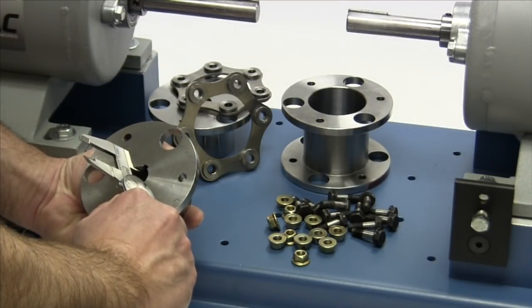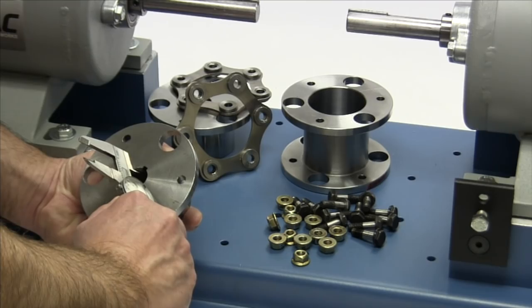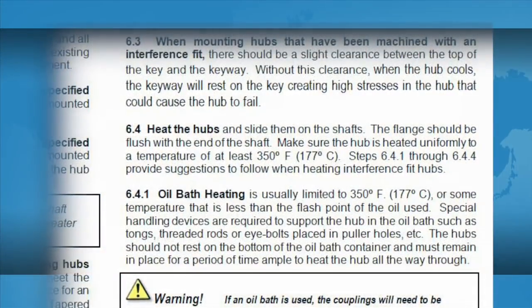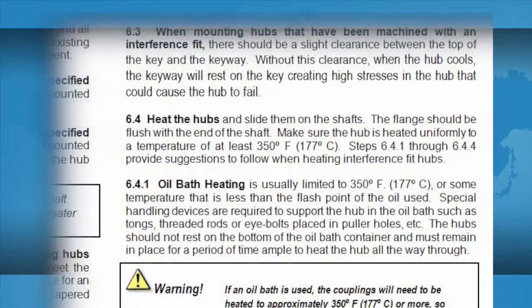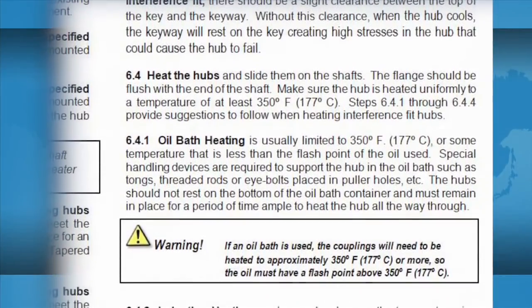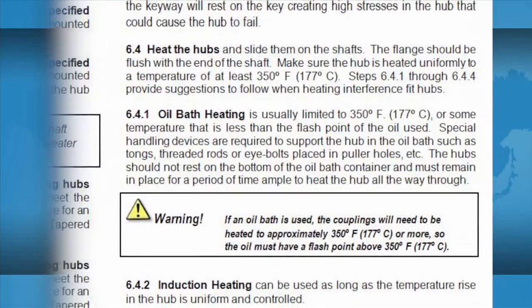You may notice the hubs are bored slightly smaller than the equipment shaft diameters. Unless otherwise specified, Lovejoy manufactures disc coupling hubs with an interference or shrink fit, and the hubs will need to be heated prior to placing them on the shafts.